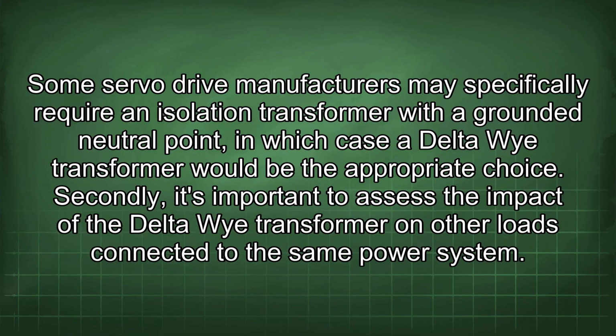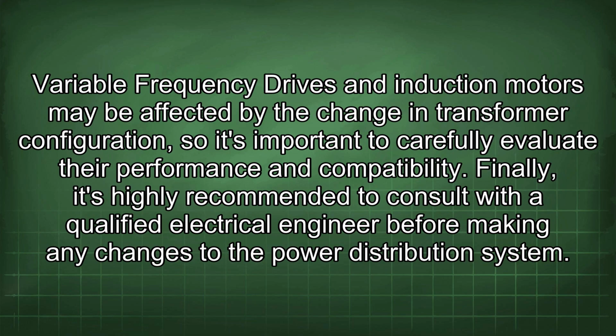Secondly, it's important to assess the impact of the delta-Y transformer on other loads connected to the same power system. Variable frequency drives and induction motors may be affected by the change in transformer configuration, so it's important to carefully evaluate their performance and compatibility.